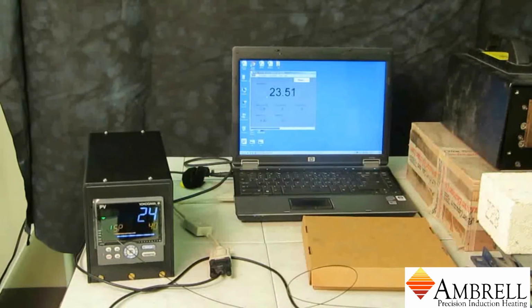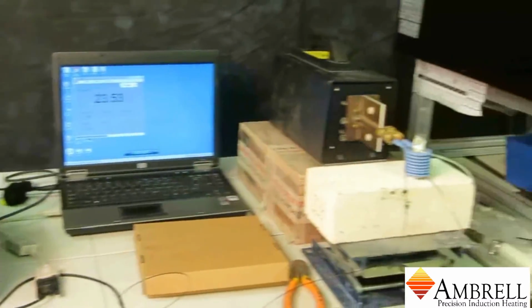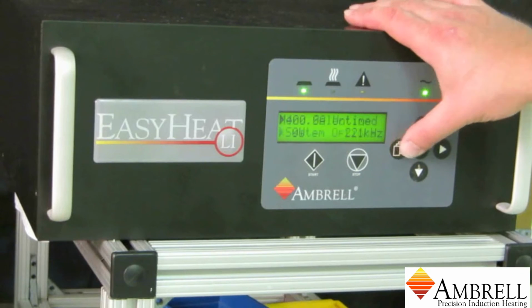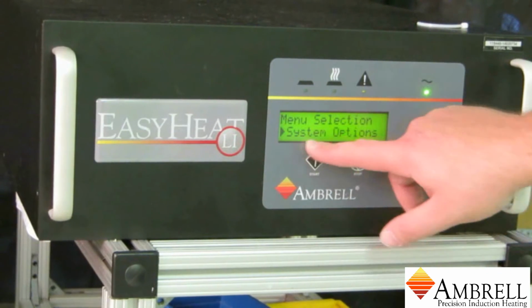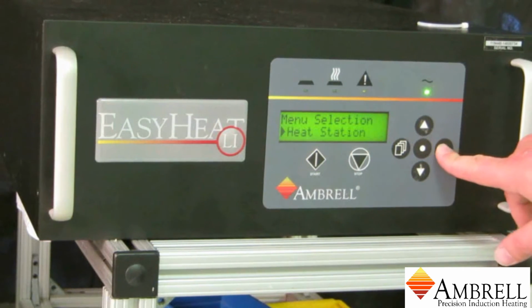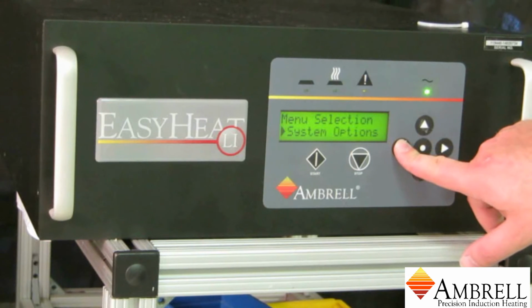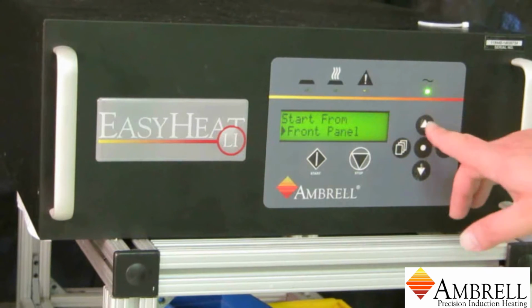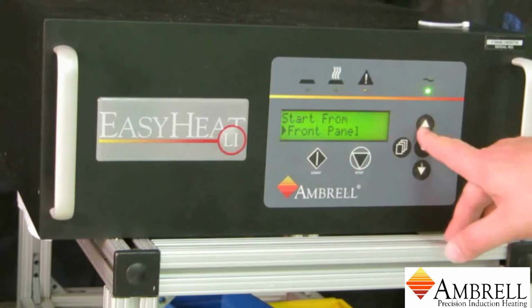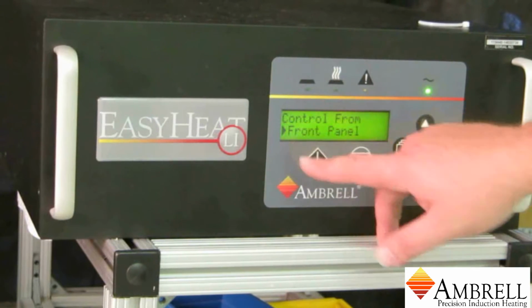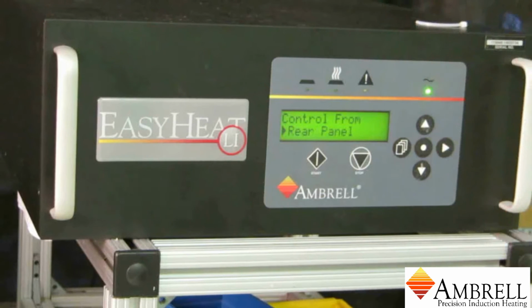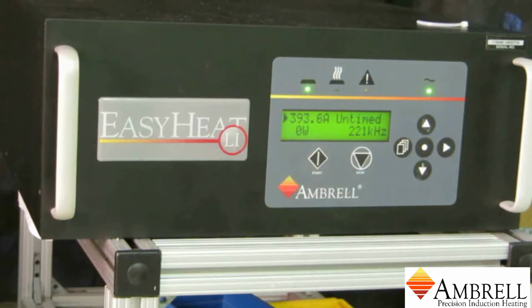I'd like to run the program that is in the Yokogawa controller now. So I have to come over to the Easy Heat Li and tell it to accept the rear input. Alright, now we'll go into the menu. Use the right arrow until we see System Options, which we see right now, and then you hit Menu. Then I'll hit the up arrow until it says Control From. Right now, Front Panel is selected, and we want it to say Rear Panel. Once that's selected, the Easy Heat Li will automatically run from the Yokogawa unit.